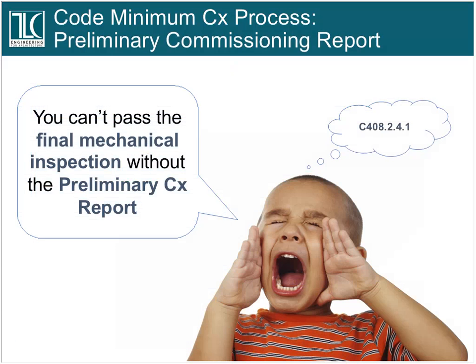Now, I can't emphasize this enough. You can't pass the final mechanical inspection without a preliminary commissioning report. So imagine, if you will, everybody shows up on Friday, the owner's going to move in on Saturday and occupy the building on Monday. The code official walks up and says, okay, where's the preliminary commissioning report before I can do your mechanical final inspection so you can occupy the building? And Bubba turns to Billy Joe and says, where's my commissioning report, Billy Joe? And Billy Joe turns to Bubba and says, what's commissioning?